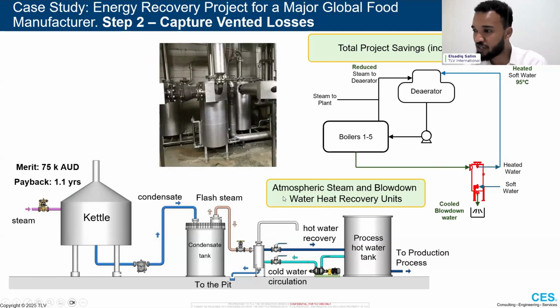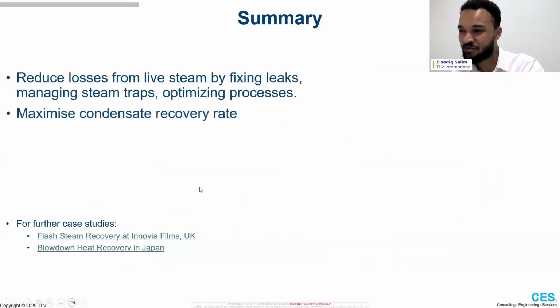Just to make a quick note, it is absolutely critical that these heat exchangers put no back pressure whatsoever on your processes, because if you put some back pressure on this condensate return tank, suddenly your process is affected. Same thing with the boiler. So sorry for speeding through that. I'll just do 3 points, and we've got some further case studies there at the bottom.